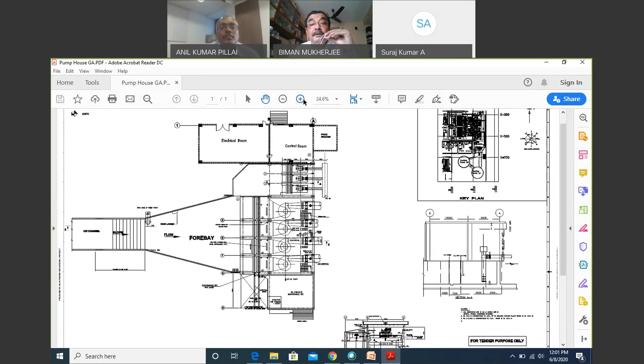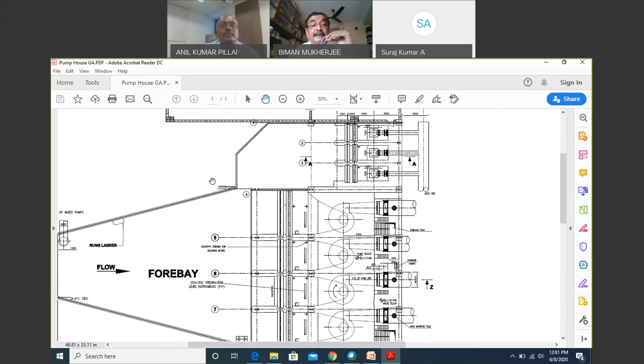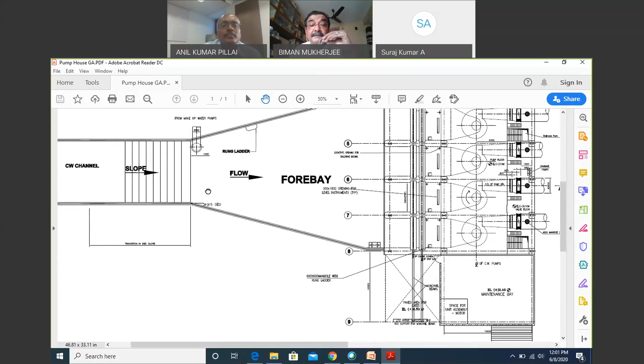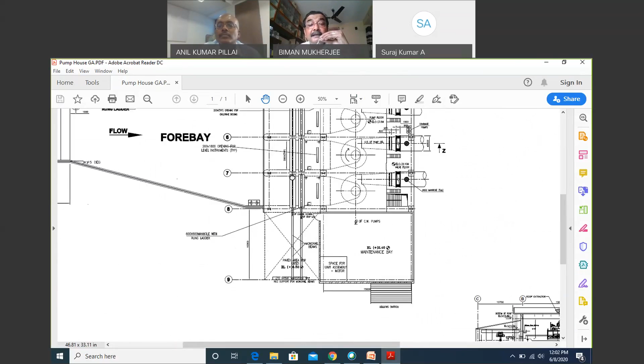Is it visible? I am trying. This is a forebay, and this is one difficult area. It is quite deep—sometimes the section is 12 meters, 18 meters deep, depending on the design. There are pumps separated from each other, and that separation distance should be decided based on the pump size and pump manufacturer. In this forebay, you cannot put any obstruction or support, so there should be no water leakage, meaning it has to be a structural slab.